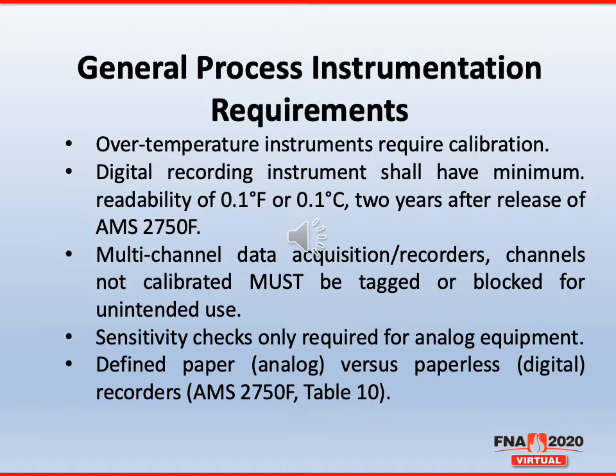Likewise, in AMS 2750, the accuracy requirements for those instruments is plus or minus 2, or as I mentioned before, 1.1 Celsius, or 0.2% of reading, whichever is greater. Again, if the instrumentation does not have a readability of 0.1, then how would you show compliance? And originally, in the first several drafts of AMS 2750F, this was required on all digital instruments. But we compromised and made it for only data acquisition systems, since that is the permanent record.